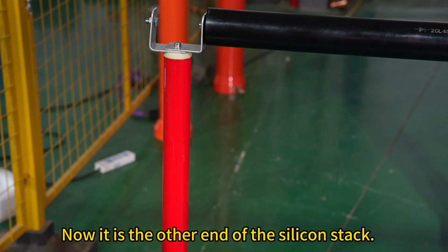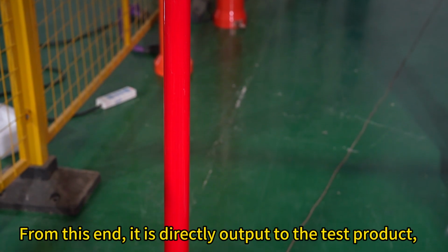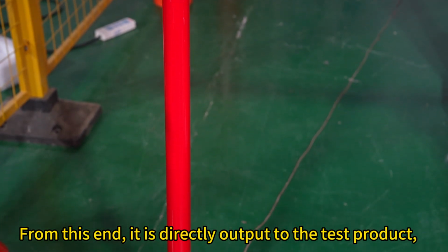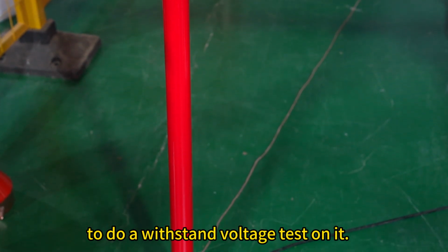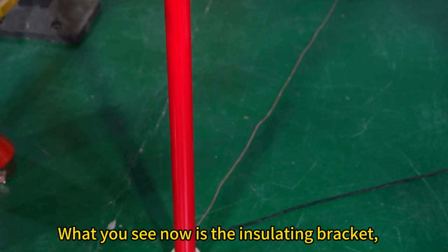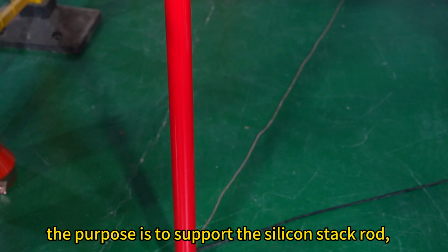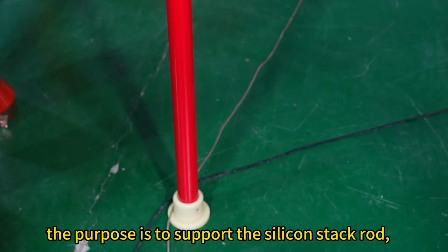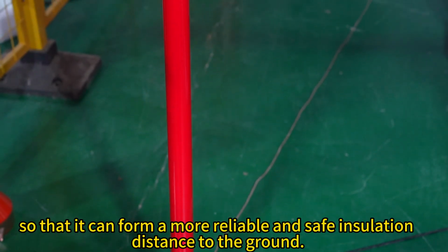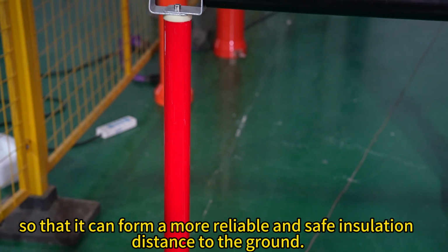Now it is the other end of the silicon stack. From this end, it is directly output to the test product, to do a withstand voltage test on it. What you see now is the insulating bracket. The purpose is to support the silicon stack rod, so that it can form a more reliable and safe insulation distance to the ground.